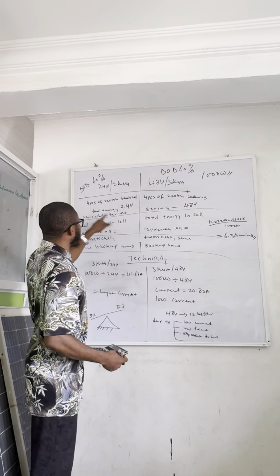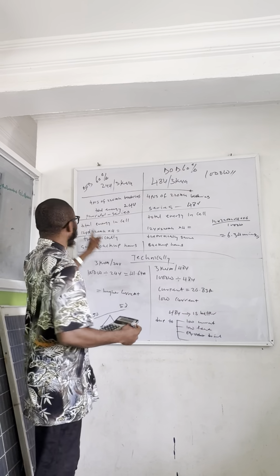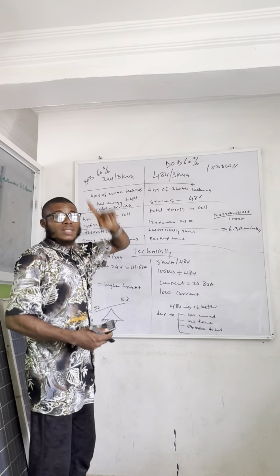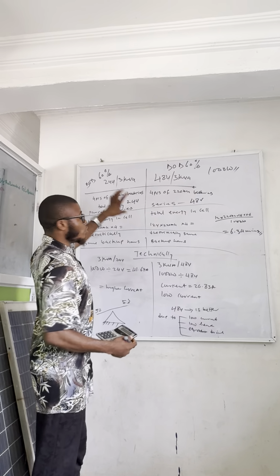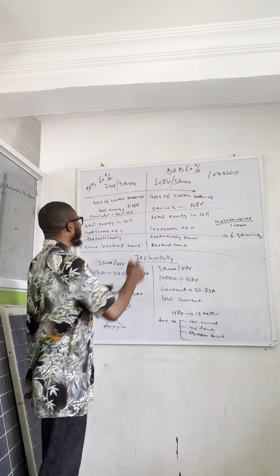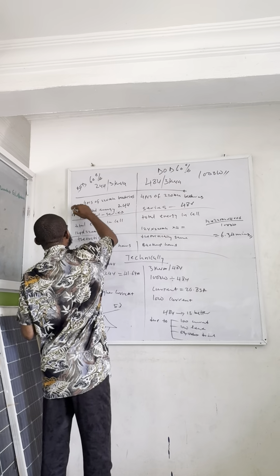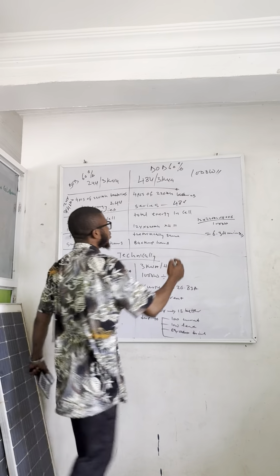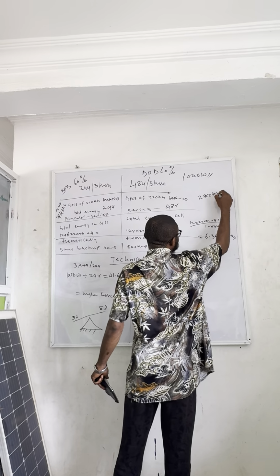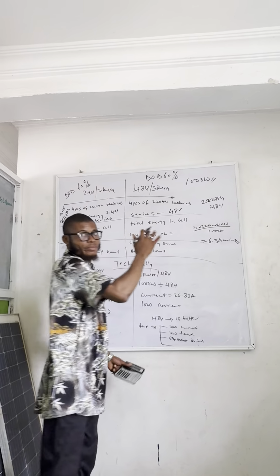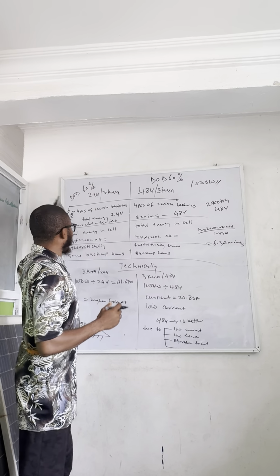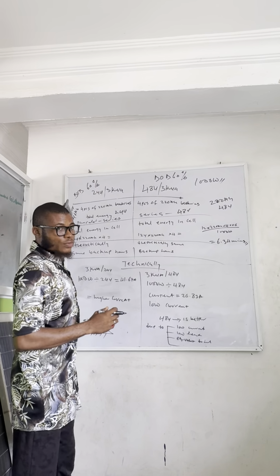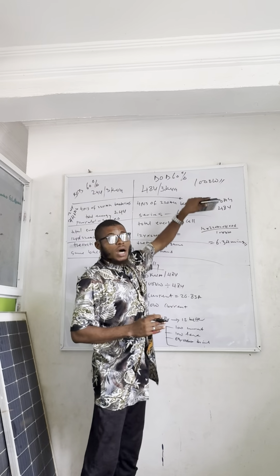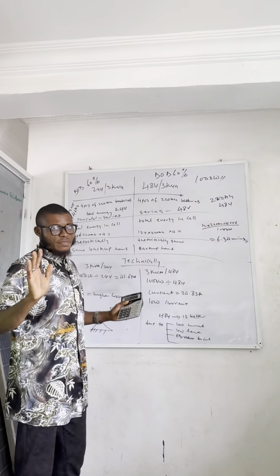For you to achieve your 24 volts, you have to do what we call a parallel series connection. When you do a series connection, you get your 24 volts. Then you do a parallel connection, you still get your 24 volts. That means you will have 440 amps at 24 volts for this one. Then you will have 220 amps at 48 volts for this system. If you do a series parallel connection, you have the 440 amps connection for this 24 volt, and you have the 220 amps connection on 48 volts. Now that is very clear.